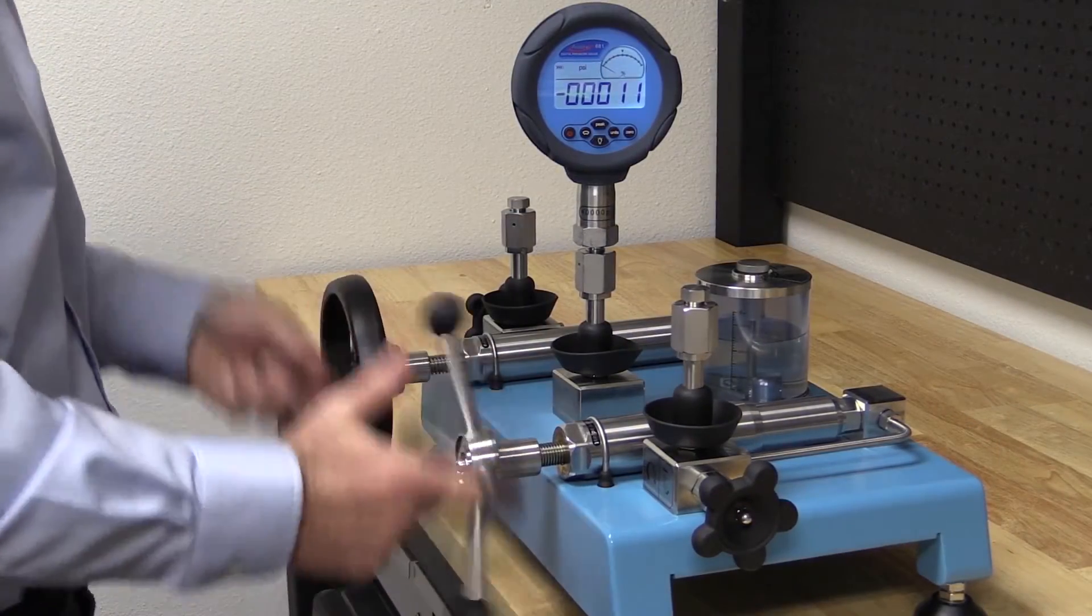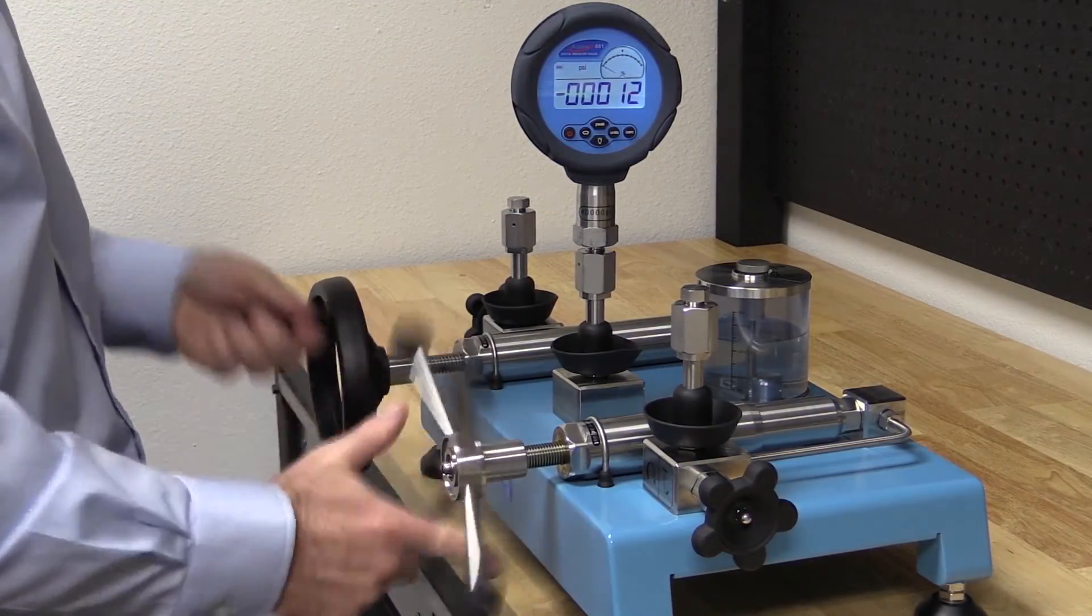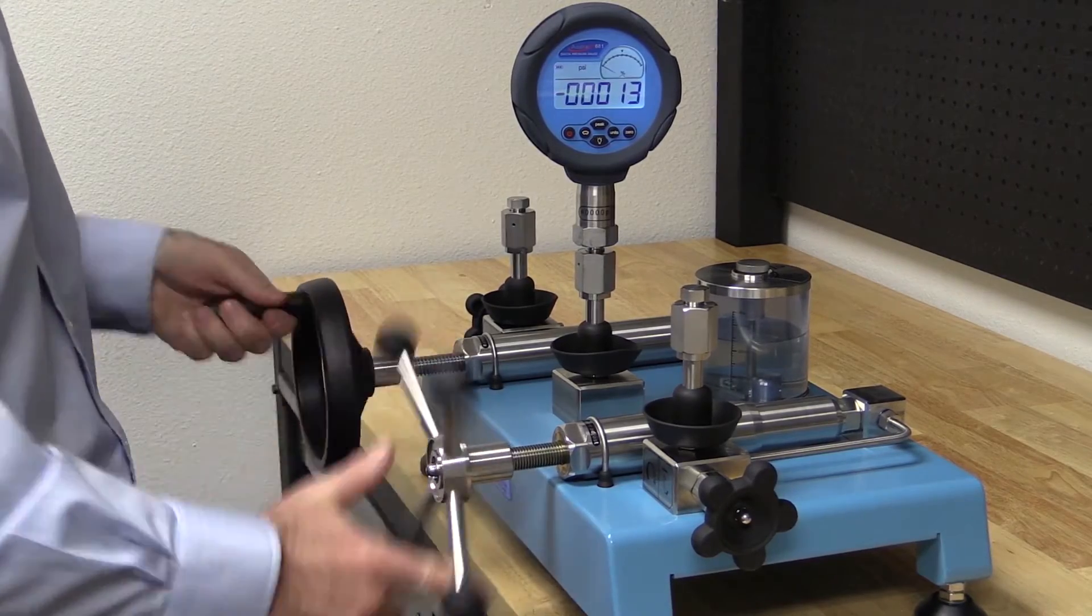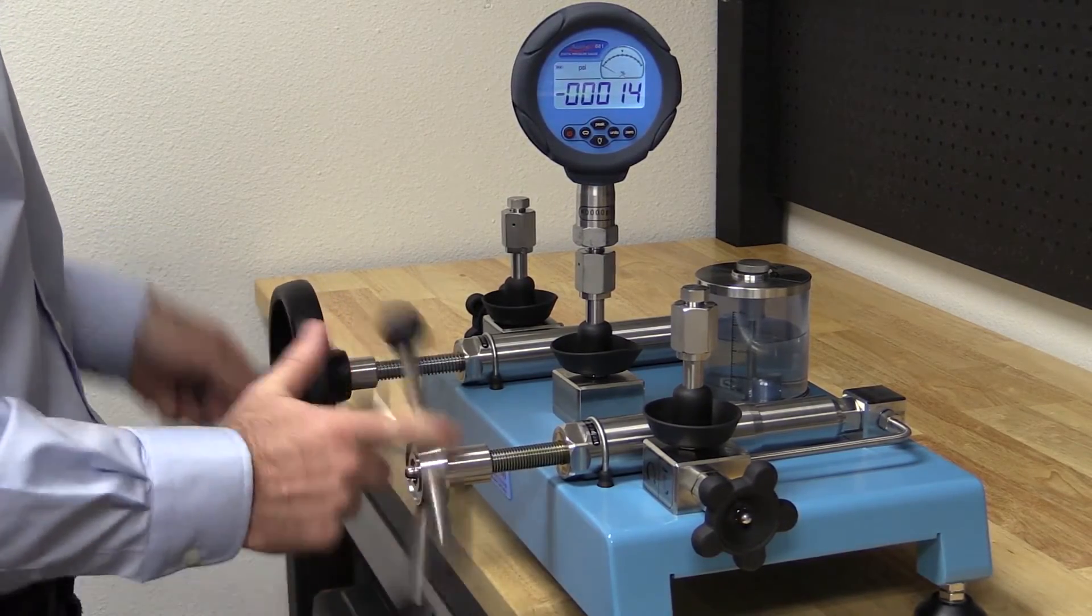Particularly on the initial setup, where there is a lot of gas in the system, the process of pulling a vacuum and purging the gas out of the system will need to be repeated several times.